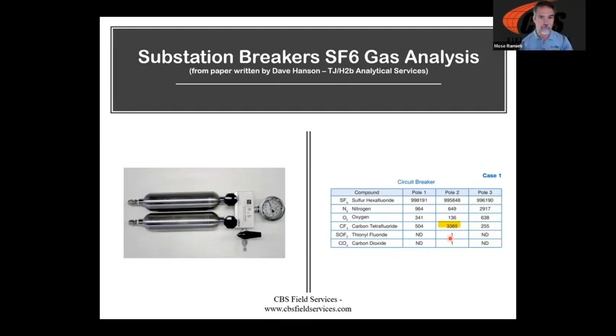And here's a great example that I took from a paper by the company. They had a breaker that they were concerned about. So they did some of this testing that I'm talking about, where they took the sample using this bottle kit, sent it to the lab, and it came back with carbon tetrafluoride, once again, a decomposition product of the Teflon material that made up part of the breaker. And after getting these results, they decided they would take that breaker out of service, take it to the factory, tear it down, and sure enough, significant damage was noted on pole 2 that was not noted on poles 1 and 3. So once again, this is a great thing. Just like a transformer oil test report, an SF6 breaker test report is fantastic.